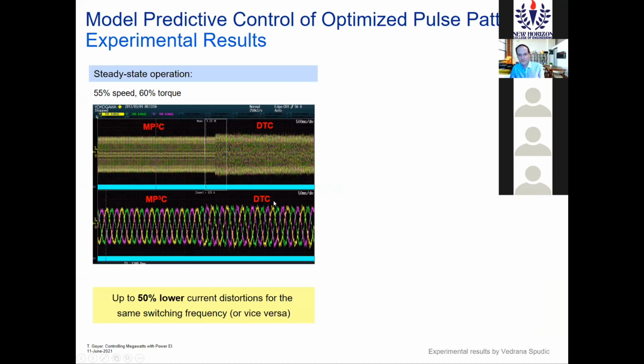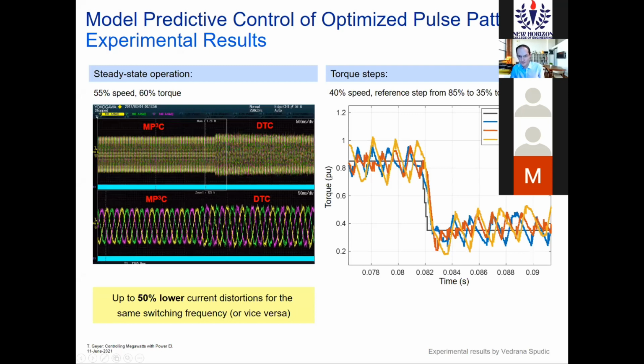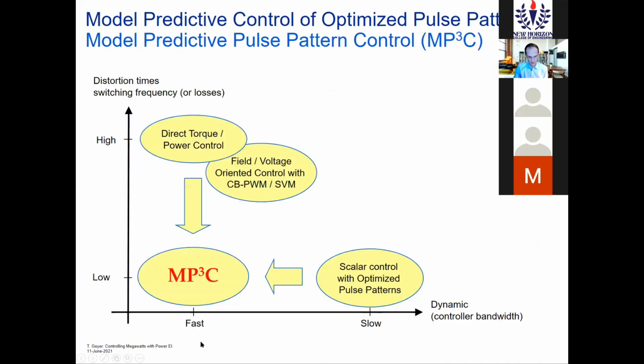If we apply torque steps, then the blue one would be the old method, and the predictive method would be the red or the yellow one, depending on the switching frequency. You see that the time it takes till you hit the new reference is exactly the same. It's around a millisecond. So the dynamic performance is similar to the established method, which was considered to be the fastest possible. So one could then claim that this MP3C, model predictive pulse pattern control, sort of squares the circle by combining the benefits of direct torque control in terms of dynamic performance with the steady state performance of optimized pulse patterns.